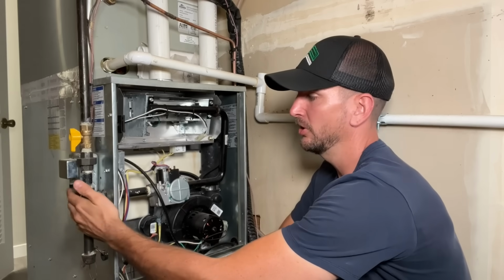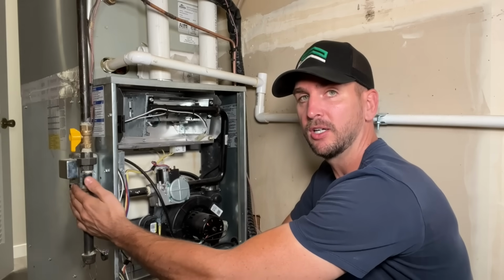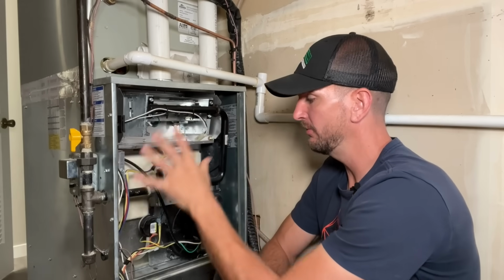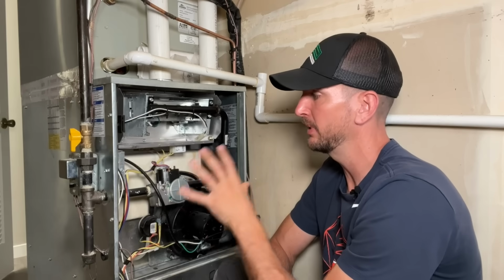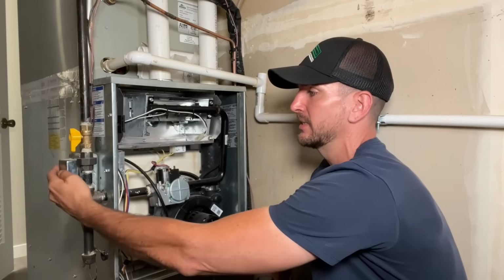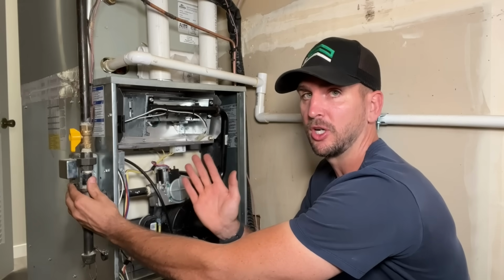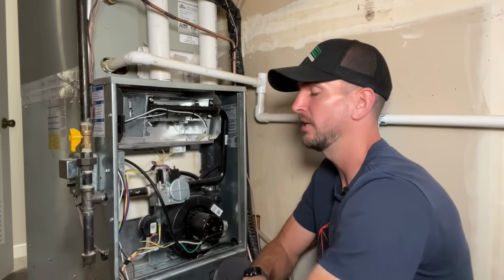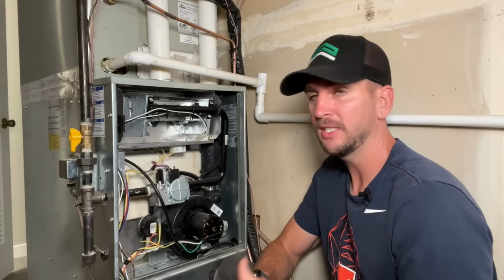So I'm going to turn on my furnace. You usually should have an on-off switch, and you should be off if you're poking around inside your furnace, but I want to run through the cycle and show you guys the 6 steps involved in startup of the furnace. So I'll flip that on. My thermostat's calling for heat.